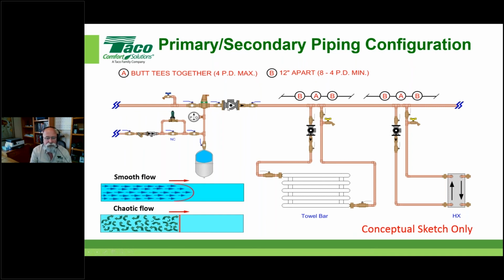But notice this: if I come out of this circulator downstream right after here, I'm going to be in a chaotic flow pattern because of what the circulator did by adding that mechanical energy to the fluid. It's going every which way. But once it goes out on this straight piece of pipe for a certain amount of distance, it goes from chaotic flow back to a nice smooth flow pattern before it gets to this first T. This is what we're talking about right here.